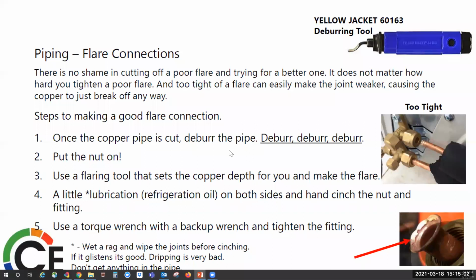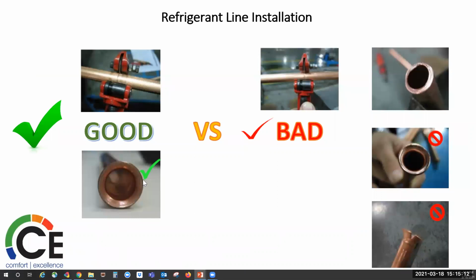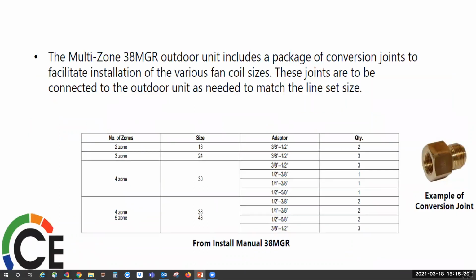This down here in the corner is an example of a bad flare. I guarantee you that's going to leak. The deburring tool was not used. There's a nice smooth one there on that one. You want a nice sharp pair of tubing cutters. For flare conversion, if you have a larger pipe coming in, especially on the multi-head units, these conversion joints come in the loose bag of parts, in different sizes for different lines.